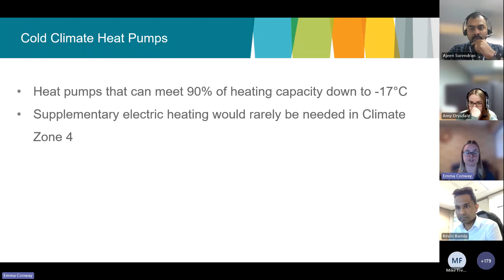There are options on the market, these cold climate air source heat pumps, that can provide the performance we want down to very cold temperatures. In a situation like this, supplementary electric heating would rarely be needed in our climate zone. So if you're worried about the costs at cold temperatures, if you install a cold climate heat pump, we're very, very rarely going to be running it off straight electric supplementary heat.